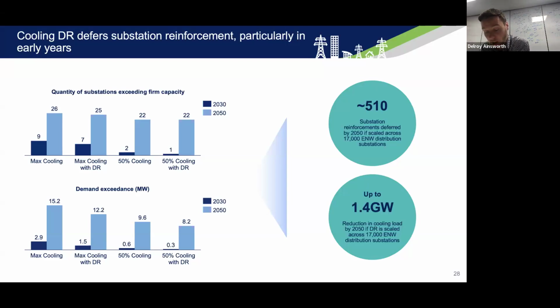The reason that the deferral rate is higher in the early years is due to the higher level of forecasted EV and HP uptake by 2050. This would therefore trigger reinforcement even without SC demand. Having said that, it's extremely likely that the forecasted EV and HP uptake will change and evolve over the years. So for this reason, it's also beneficial to look at the level of demand exceedance. And this is the level of demand which exceeds the substation rating. As you can see from the bottom graph, in max cooling scenario, this shows a demand exceedance of 2.9 megawatts in 2030 and 15.2 megawatts by 2050. Applying DR produces a saving of 1.4 megawatts in 2030 and 3 megawatts in 2050. And for the 50% cooling scenario, the demand exceedance is 0.6 megawatts in 2030 and 9.6 megawatts in 2050. Applying DR produces a saving of 0.3 megawatts in 2030 and 1.4 megawatts in 2050.